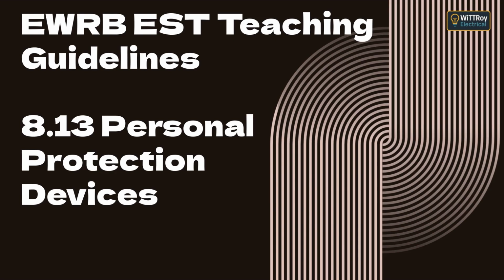Topic C. Type of RCD required in New Zealand. In New Zealand, all RCDs installed for shock protection must be Type A as specified in AS/NZS 3190 and AS/NZS 3000 Clause 2.6.1. Type A RCDs detect both pure AC fault currents and pulsating DC currents, which can occur from electronic loads like washing machines or LED drivers. Older Type AC RCDs only detect pure AC and are no longer acceptable for personal protection in new installations. So, when fitting or testing RCDs, always check the label; it must show Type A.